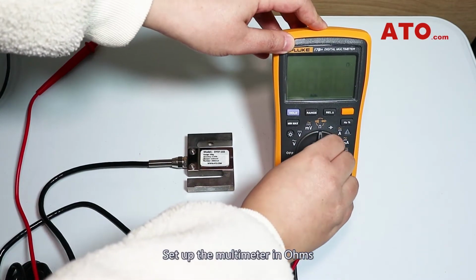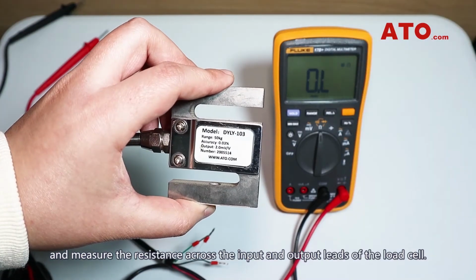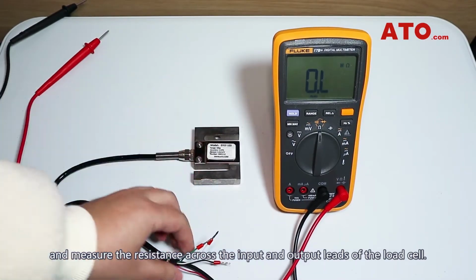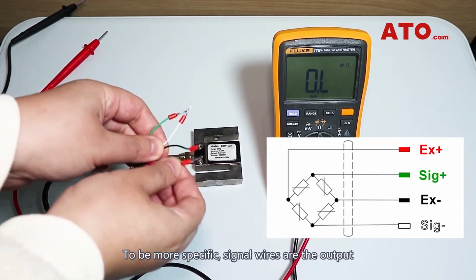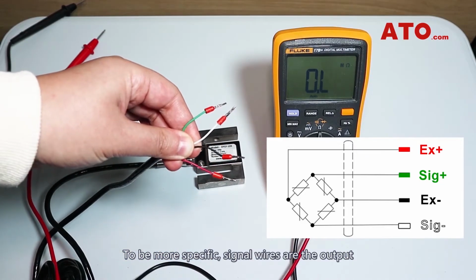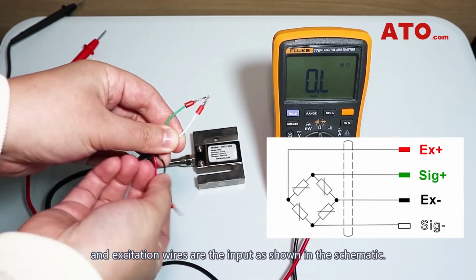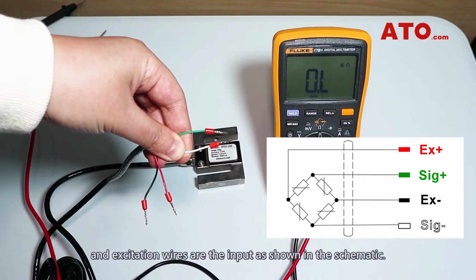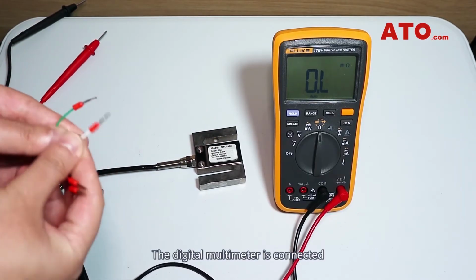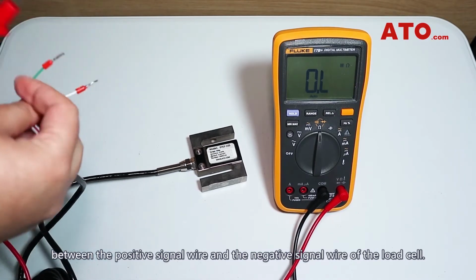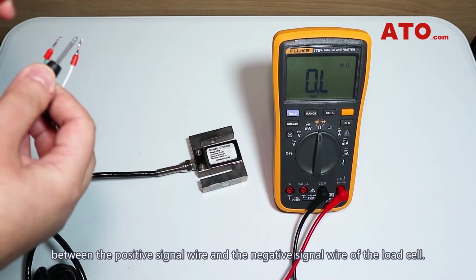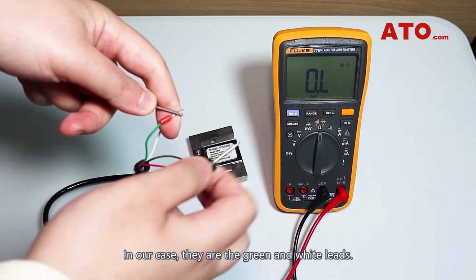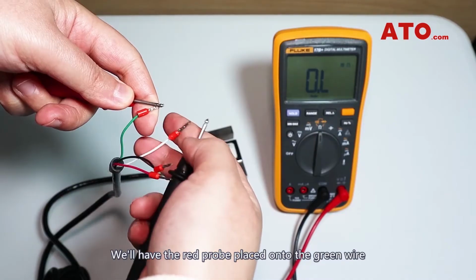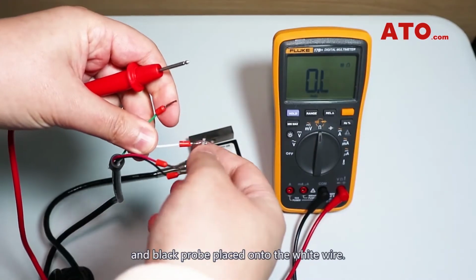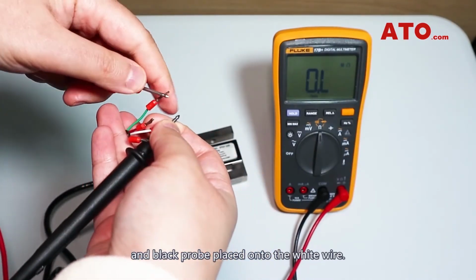Set up the multimeter in ohms and measure the resistance across the input and output leads of the load cell. To be more specific, signal wires are the output and excitation wires are the input, as shown in the schematic. The digital multimeter is connected between the positive signal wire and the negative signal wire of the load cell. In our case, they're the green and white leads. We'll have the red probe placed onto the green wire and black probe placed onto the white wire.